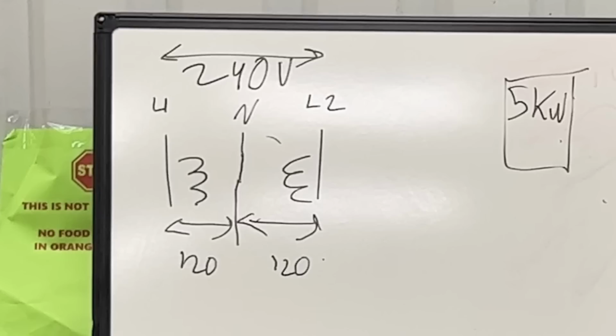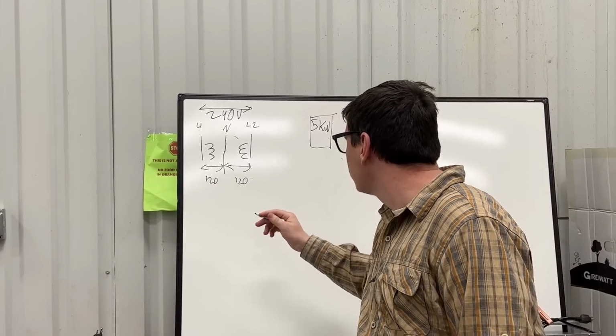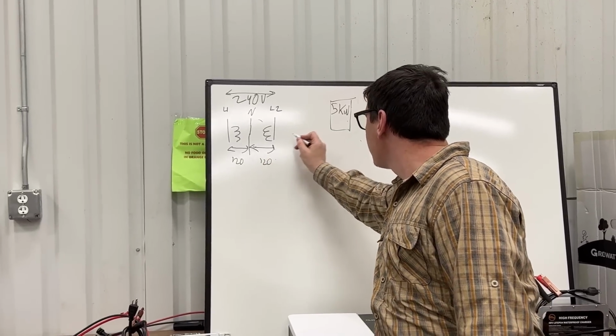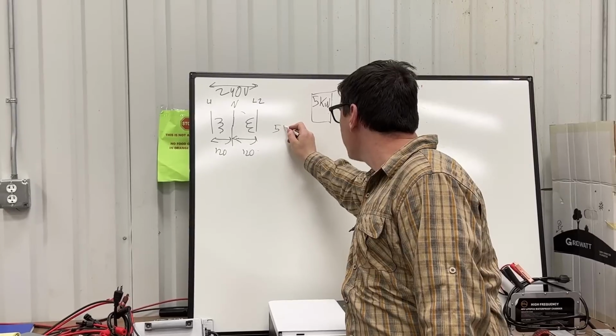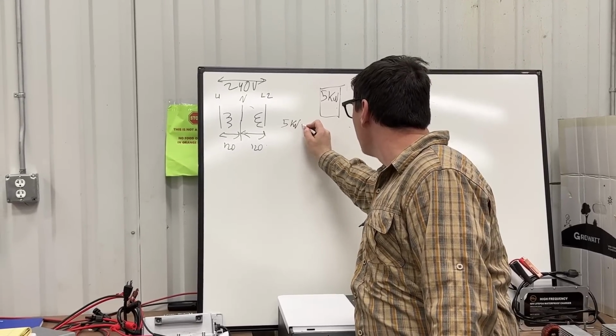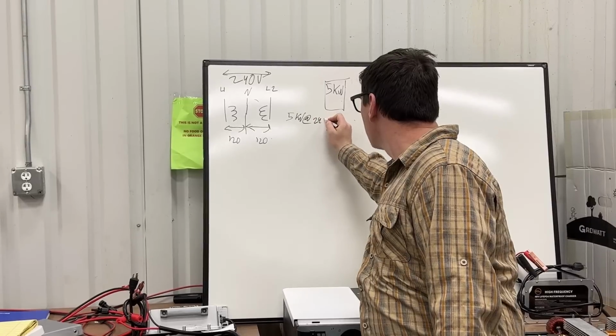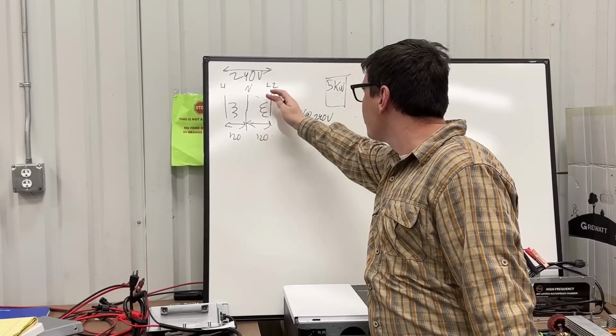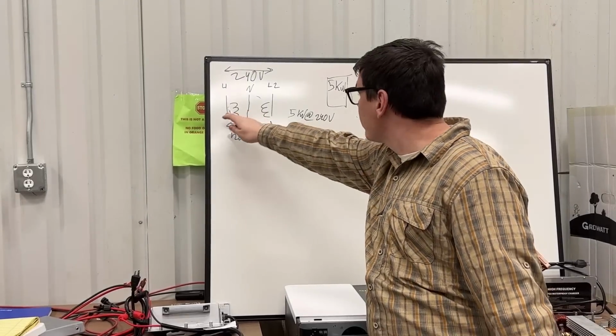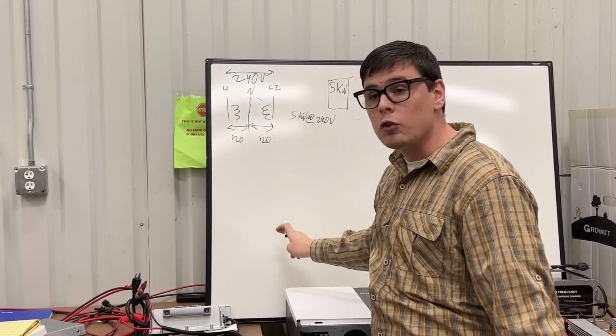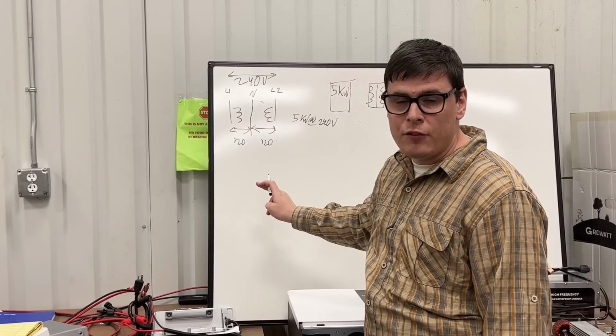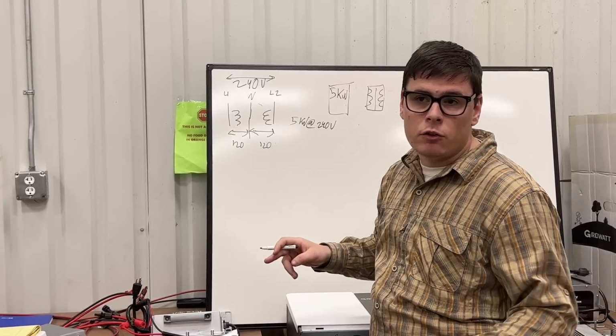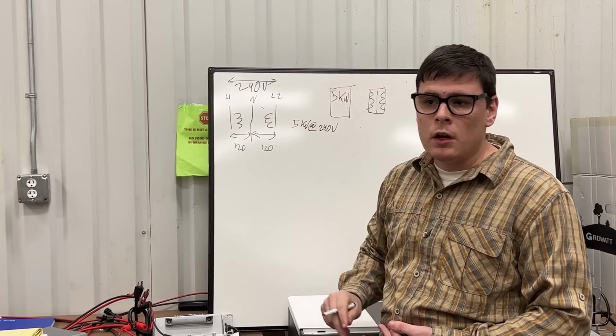And from neutral to line 1, you have 120, and neutral to line 2, you have 120. Now, that's all fine, but let's walk through a few facts here. If you have 240 volt loads, let's say we have a scenario where we're going to put 5 kW of 240 volt loads. That won't even touch the transformer. It's going to go directly from the line 1 and line 2 terminals of the inverter and feed that 240 volt load, whether it's your 240 volt mini split, your oven, your dryer.